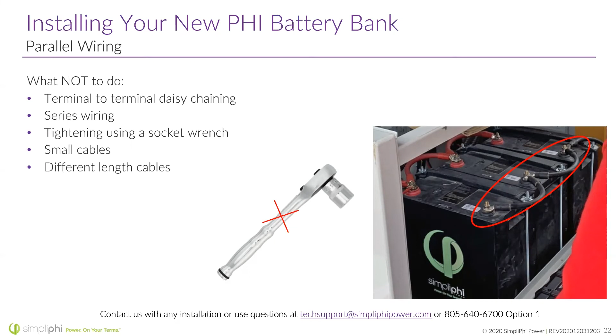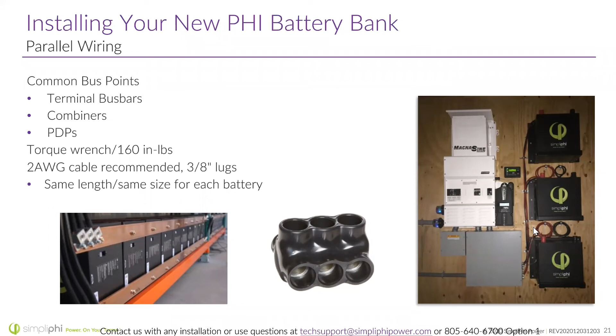Don't use small cables. So we really recommend, most of our installers are using either 4 or 2 gauge cables for each individual battery, and they're using the same gauge, same size cable, same length cable for each battery. So going back to this photo, this battery is the farthest away from the combiner. These two are a little closer, so they have extra wire coiled here, so that the battery current is traveling through the same length of wire for each battery. That's how to create a well-balanced system right there.